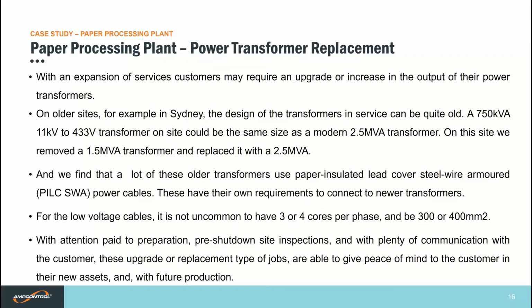We find that a lot of these older transformers use paper insulated lead covered steel wire armoured cables. These have their own requirements, of course, to connect to the newer transformers with regards to the bushing types that are used, the access and getting onto the transformers. For the low voltage cables, it is not uncommon to have 3 or 4 cores per phase and be 300 or 400 square mil in the cable size. Again, that presents its own little issues when you're trying to connect things back up.